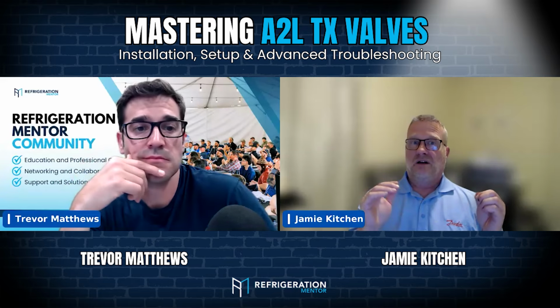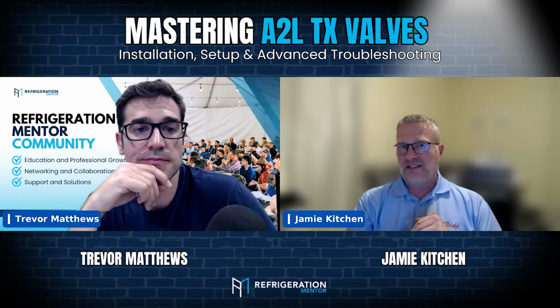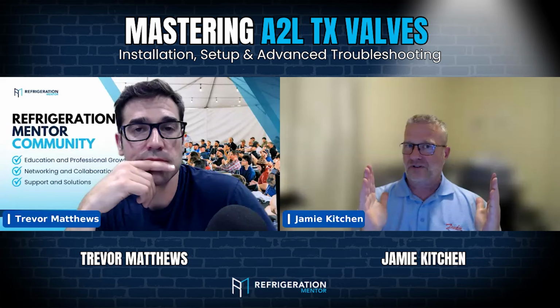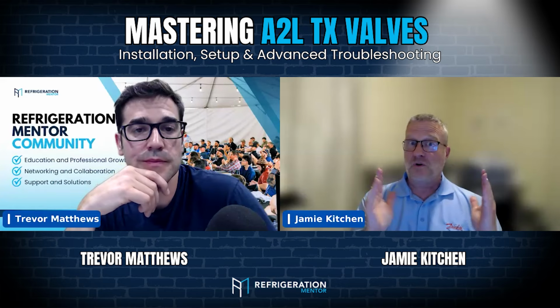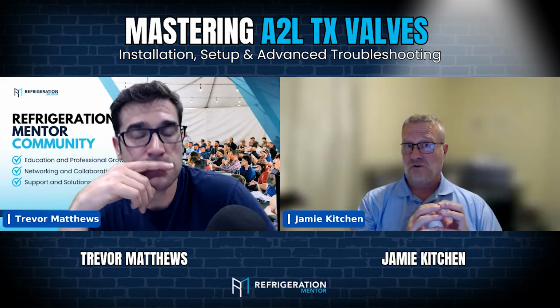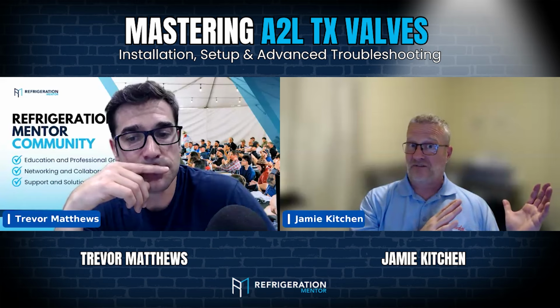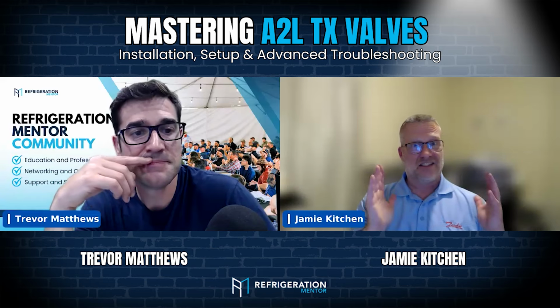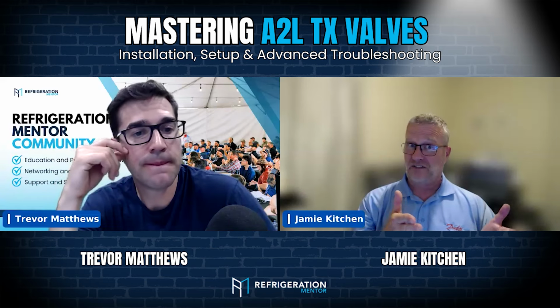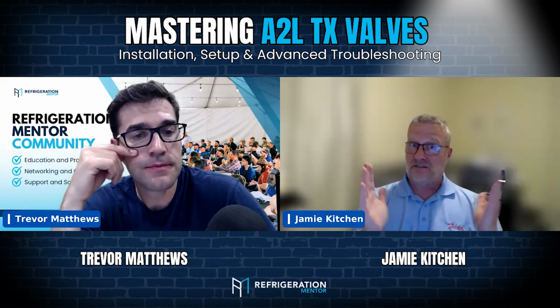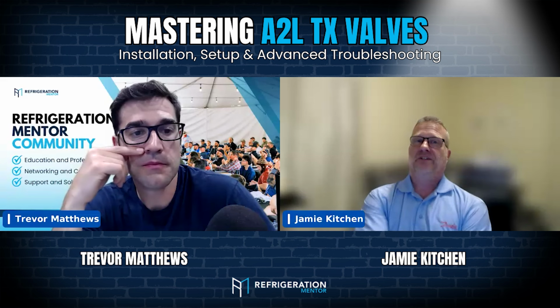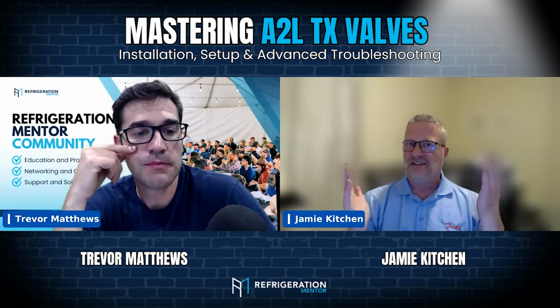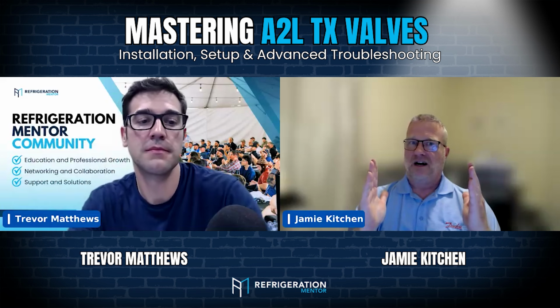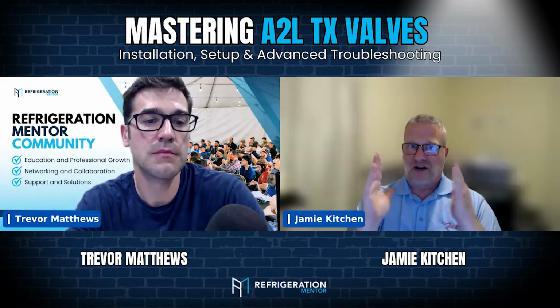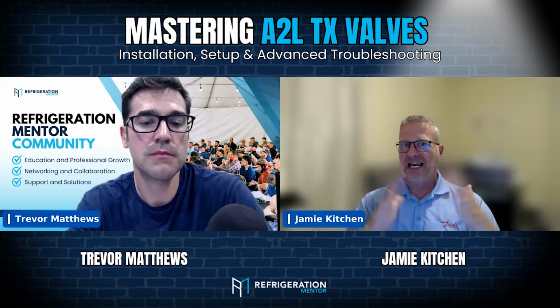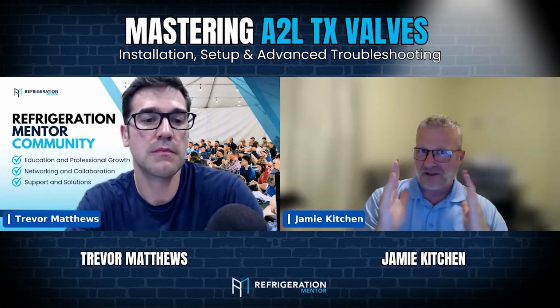Remember, if you look at the number of TXVs since 2007, when SEER 13 hit, Danfoss has the majority of the market in those controls. So there's a good chance you're going to see a Danfoss valve. I see a lot of guys doing service videos and there are Danfoss valves in there. So you can replace anybody's valve with this. It's ten times easier. And you don't have to worry about having a bunch of different valves on the shelf, because again, this gives you that flexibility.